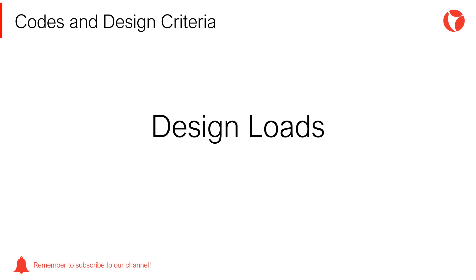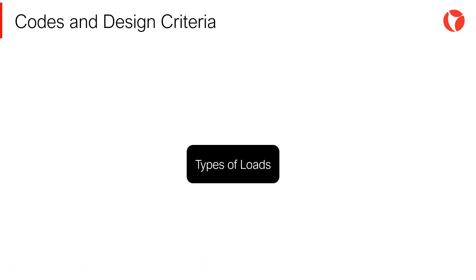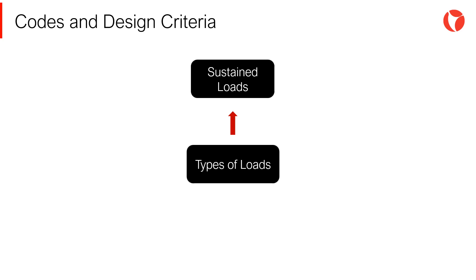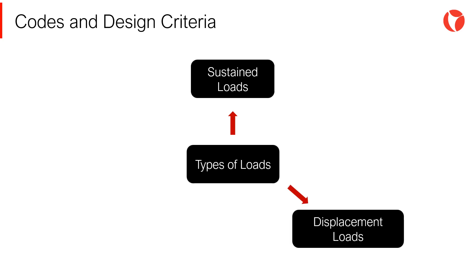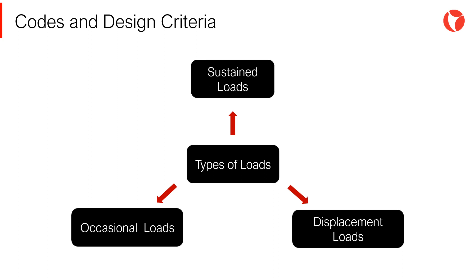There are different types of loads coexisting in a piping system which the piping designer must analyze, then select the most restrictive combination for the system — such as the hydraulic testing condition or the operation condition. In a piping system, there are three types of loads: sustained loads, displacement loads, and occasional loads.